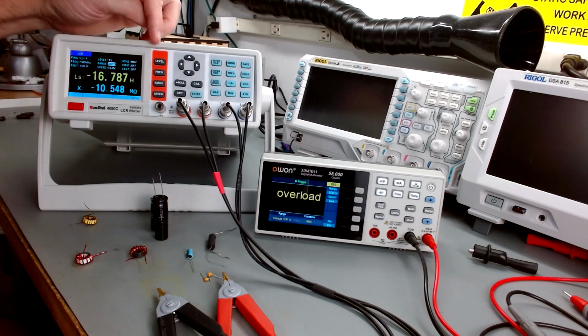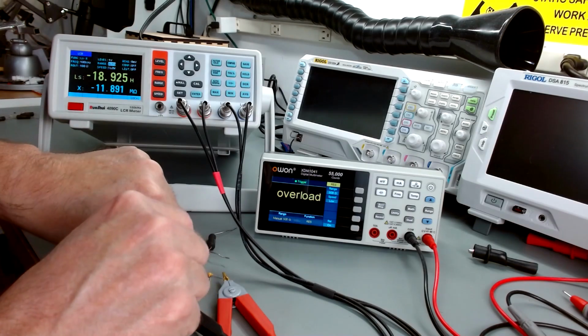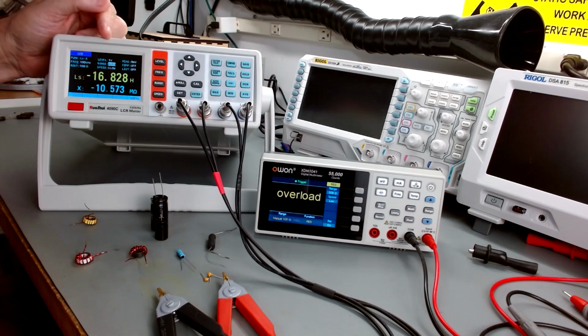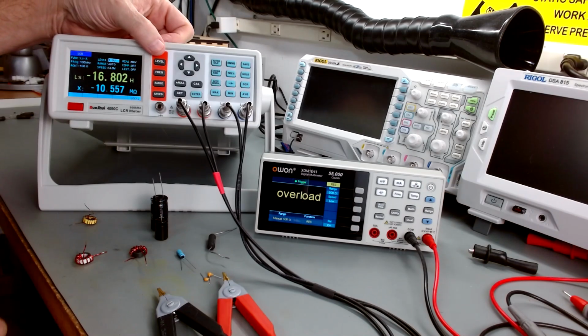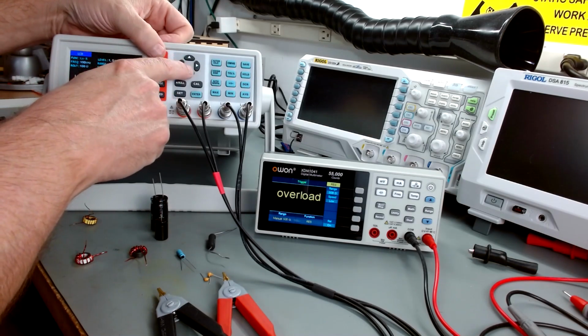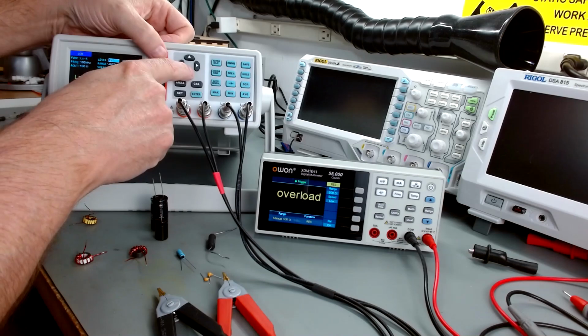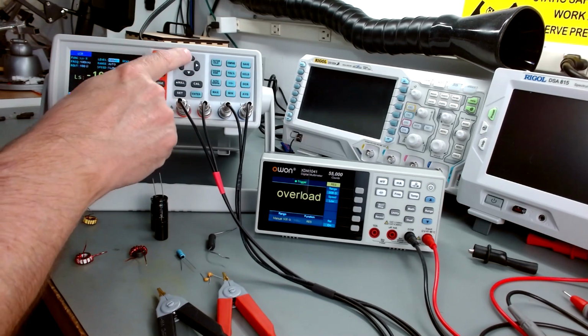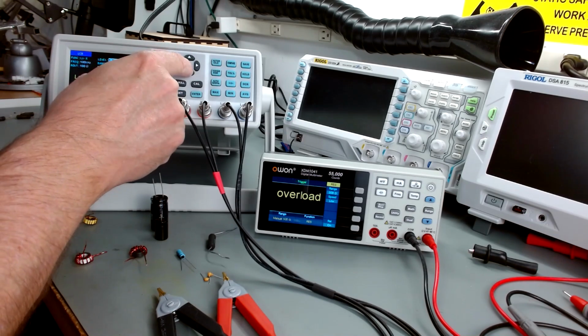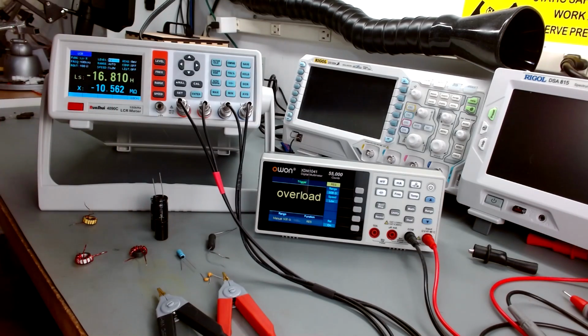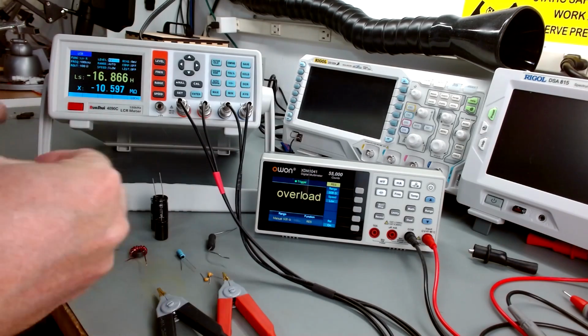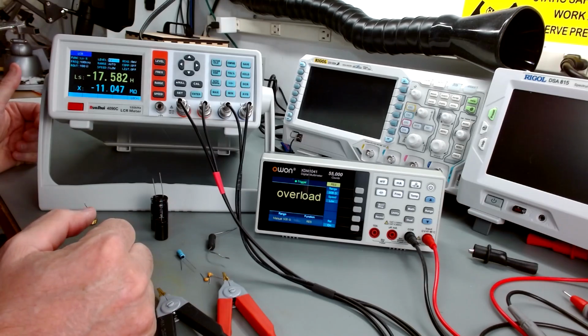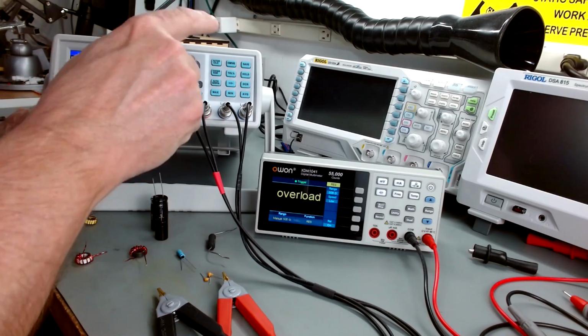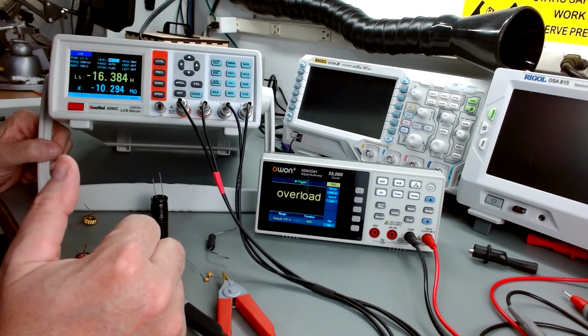The other thing you can do is the level. Currently, testing these capacitors is using 1 volt to do so, but I can hit level and using the arrows change it—there's 600 millivolts, we can go down to 100 millivolts, and as high as 2 volts. So the default is 1 volt, but you can choose that—decide you need more voltage for testing a component, and adjust the bias voltage if you have a need for that.